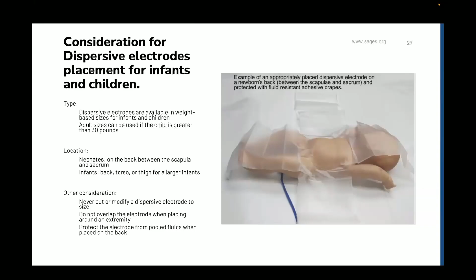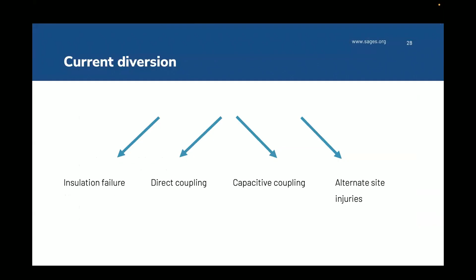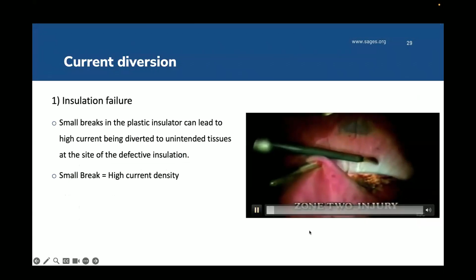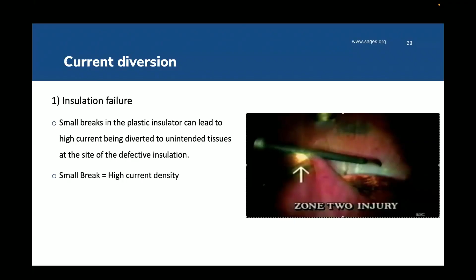Current diversion. This is the second broad category and can be divided into insulation failures, direct coupling, capacitive coupling, or alternative site injuries. I'll go over each one quickly. Insulation failures: you'd be surprised how many of these instruments that we reuse regularly can start to develop defects in their insulation. And remember, these defects can be too small to even see with the naked eye, but the smaller they are, the more they can focus current and lead to high current density areas and a high potential for injuries. So we always have to inspect and monitor our instruments before using them.